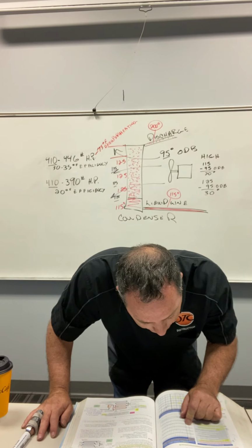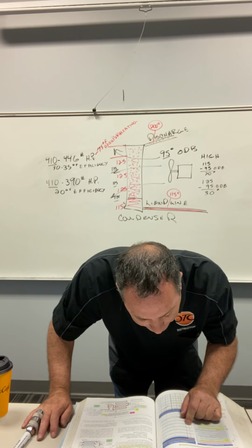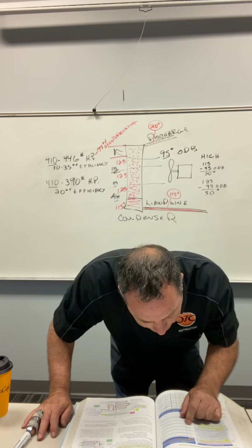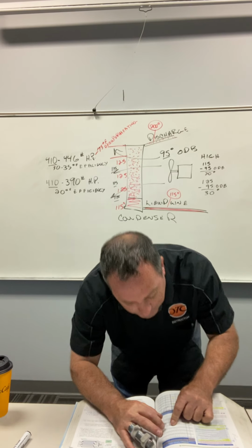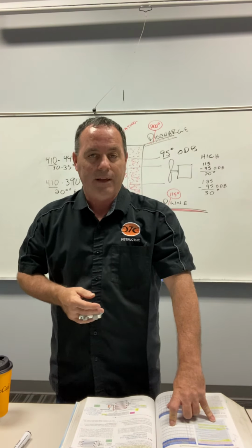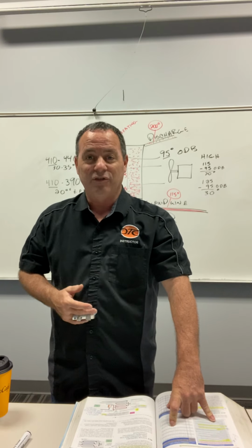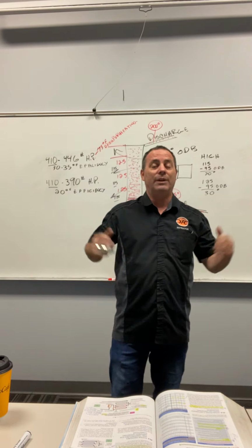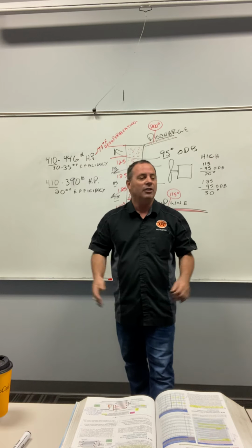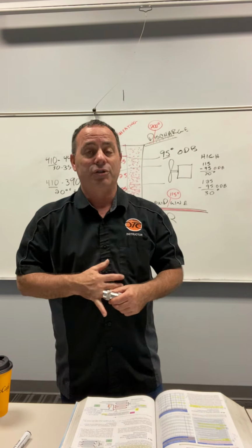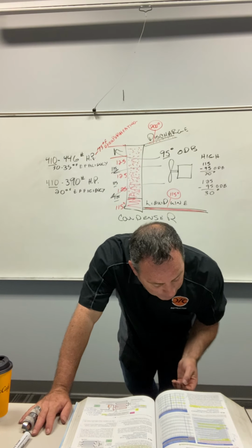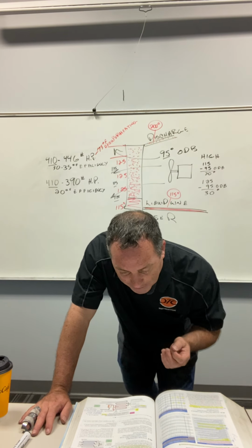And it says at the top, the indoor coil entering temperature is, with wet bulb, 64 degrees. We should have 9-degree superheat. See, they got charts for all this. All these different ranges for you, they got typical operating charts. They usually come with the unit. You take the panel off and you got the charts right there. So these help you figure out how to charge it.